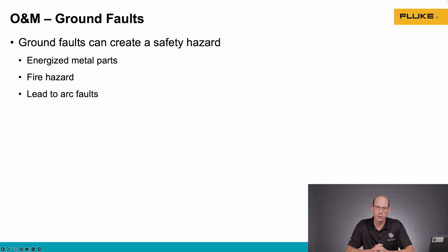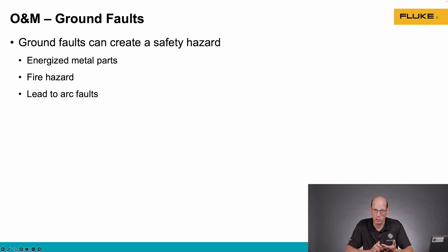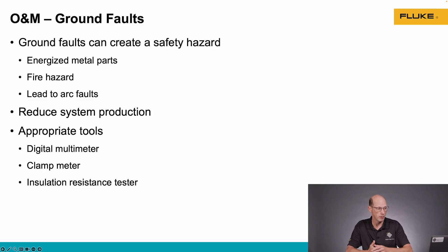Ground faults can be a safety hazard. If current's flowing to ground, it may be arcing, and that arcing can cause sparks which can cause fires. That's a safety hazard to the technician because the non-current carrying metal parts have now become energized. If the technician touches the frame of a module, they may become an easier path to ground and that's where shocks or electrocution happens. Ground faults also reduce system production because current is flowing to the ground instead of going to the load — the inverter.